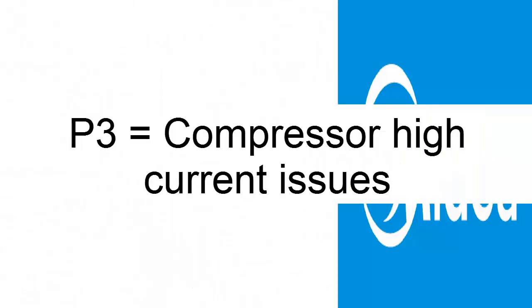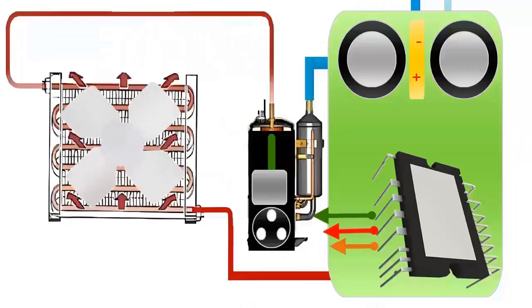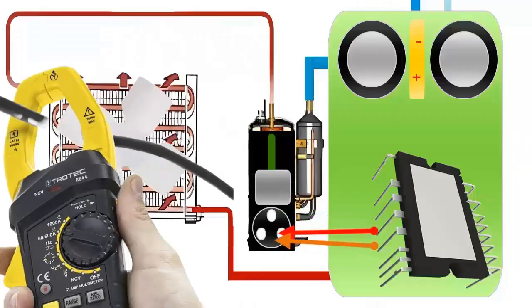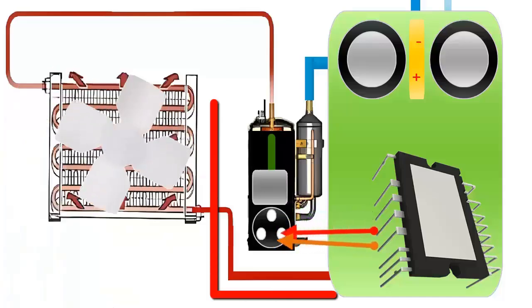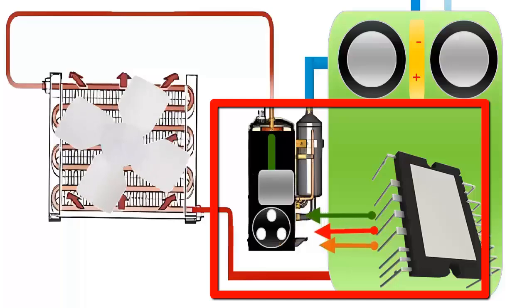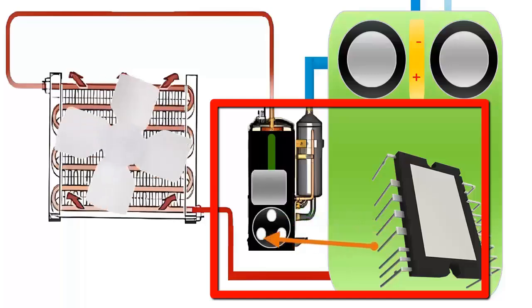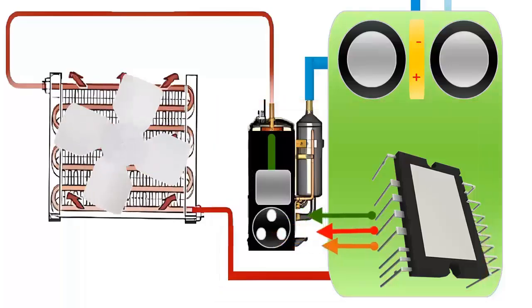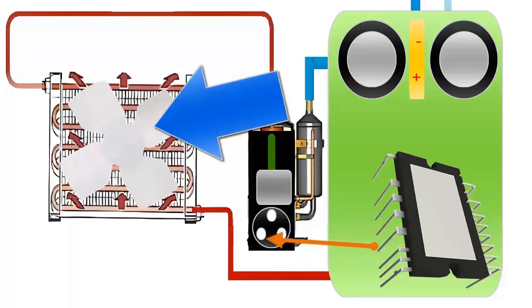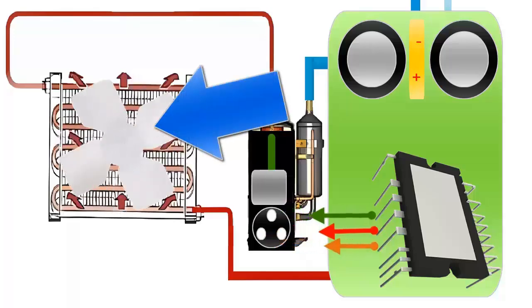Code P3 generally indicates compressor current protection. Recommendations: A. Check the condition of the compressor and the inverter module, as we will show at the end of the video. B. If Code P3 takes a long time to appear, check the airflow in the outdoor unit and the correct rotation of the fans.